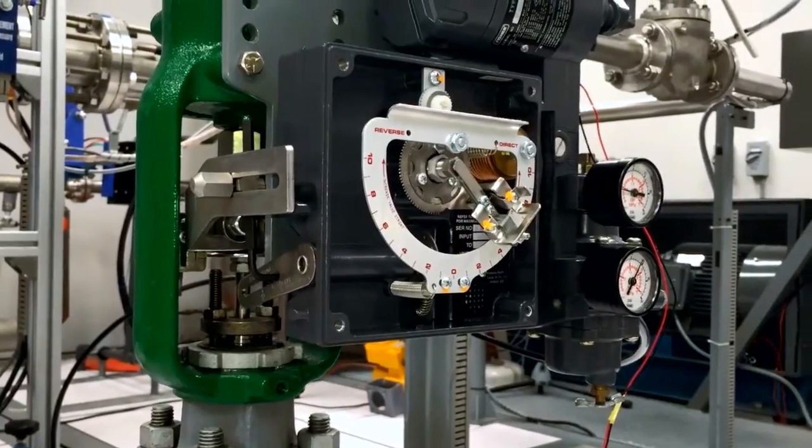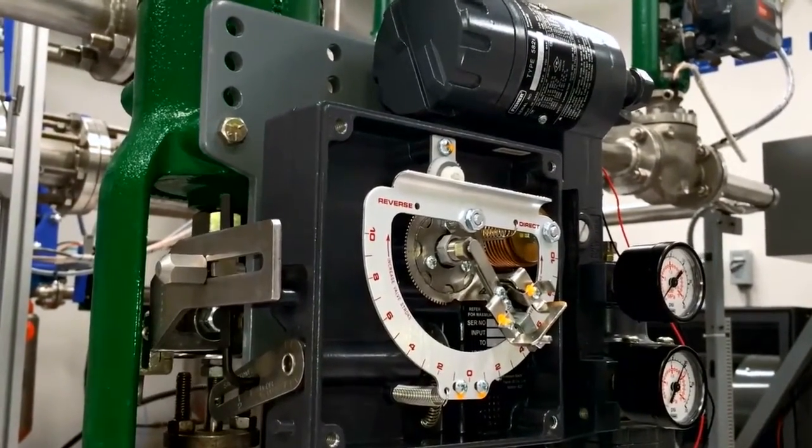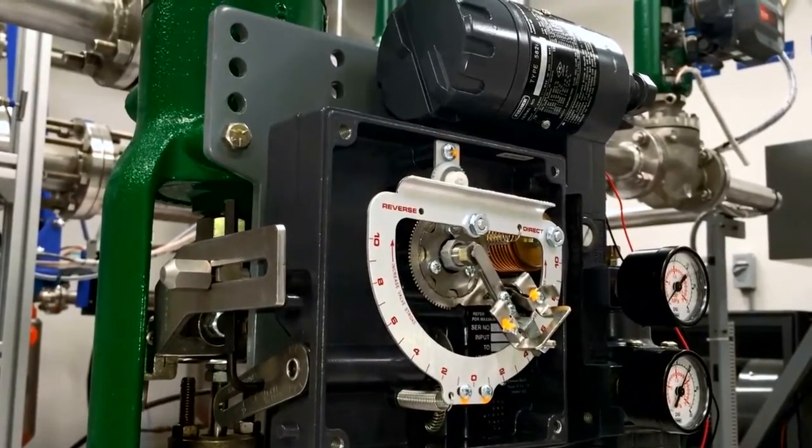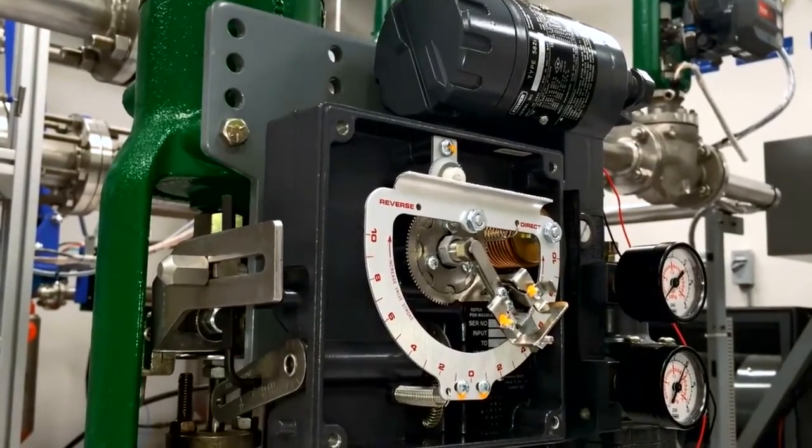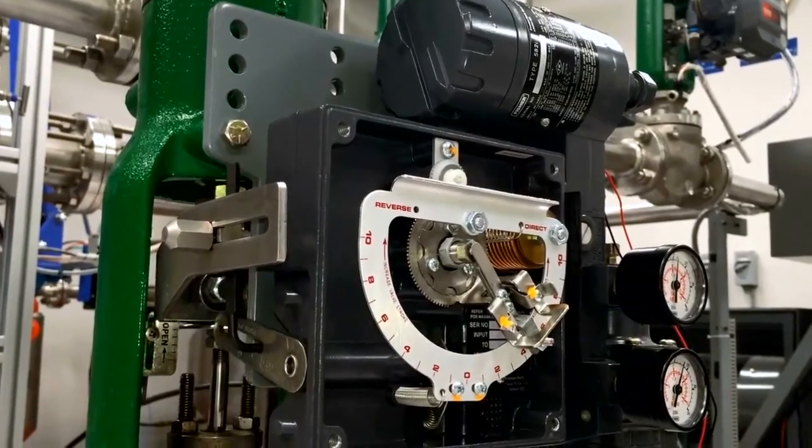After the zero trim adjustment, we apply an input signal equal to the high value of the input signal range, in this case 20 milliampere, and observe the actuator stem.